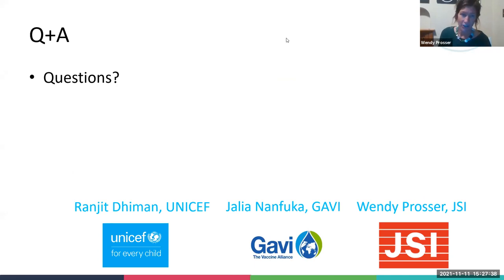All right. So let's start with the dial thermometers and stem thermometers. Ranjit, if you could give a bit of insight into those. I don't see the question in the list on dial or stem, but the idea is, now we are moving ahead with 30 DTR as one mandatory temperature monitoring device in the fridge, and one of these needs to stay in the fridge as a backup device just in case 30 DTR is out of battery or malfunctioning. So then it's just one backup device to check temperature. But now the guideline is to have 30 DTR as one standard temperature monitoring device.